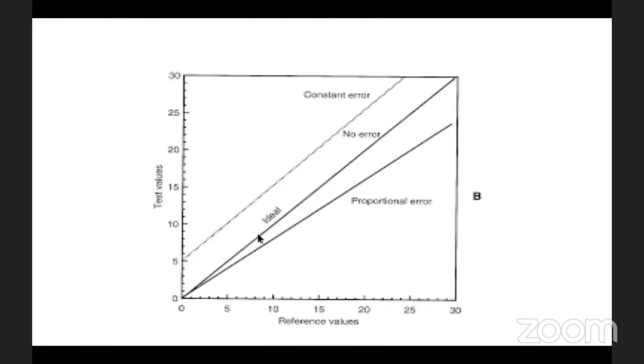And to bring objectivity into the system, you can take the help of the Westgard website, because this calculation formula is a very cumbersome formula. But on the Westgard website, you put in machine A readings, which you have plotted on the x-axis, then machine B readings, which you have plotted on the y-axis, and when you submit, you get a graph of this type and one R2 value, that is the correlation coefficient. If it is more than 0.90, that means this is very good correlation. If it is more than 0.95, this is excellent correlation. This should be as close to 1 as possible.